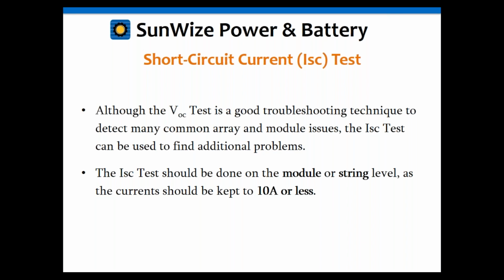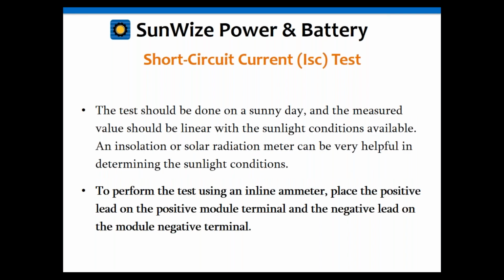So what was happening was there was enough of a connection that it was okay to measure the voltage, but there wasn't enough contact metal there for the current to flow. So when we did the short circuit current test, we found out there was a problem there. That's one of the things you can find with that. And then we were able to backtrack and find out that it was almost a full turn on that screw in the solar module, and that was it. It was that simple. Unfortunately, the system went down because of that. And again, I'll get back to maintenance. Doing proper preventative maintenance can prevent things like that from happening.